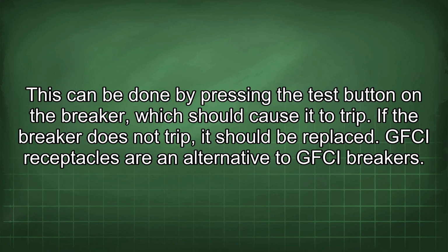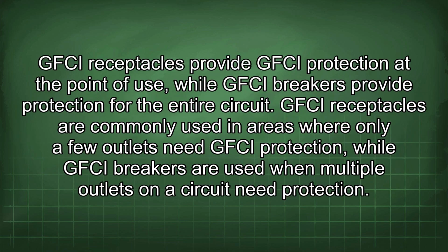GFCI receptacles are an alternative to GFCI breakers. GFCI receptacles provide GFCI protection at the point of use, while GFCI breakers provide protection for the entire circuit. GFCI receptacles are commonly used in areas where only a few outlets need GFCI protection, while GFCI breakers are used when multiple outlets on a circuit need protection.